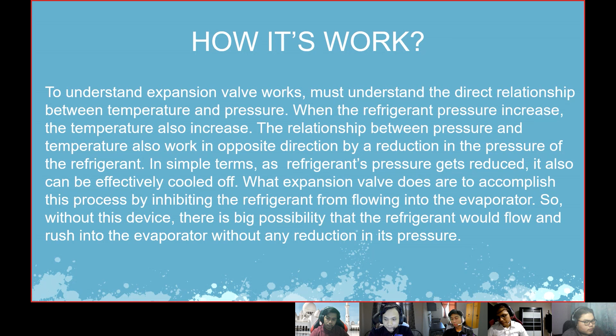What the expansion valve does to accomplish this process is inhibit the refrigerant from flowing into the evaporator. Without this device, there is a big possibility that the refrigerant will rush into the evaporator without any reduction in its pressure.